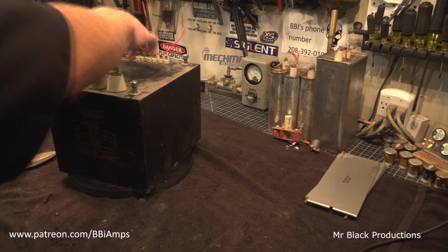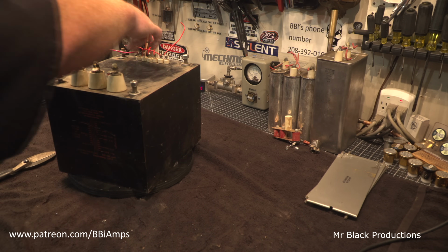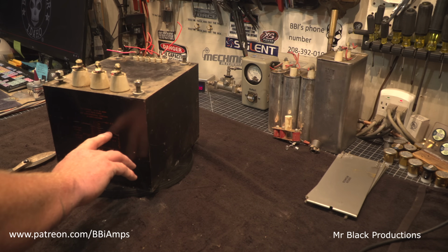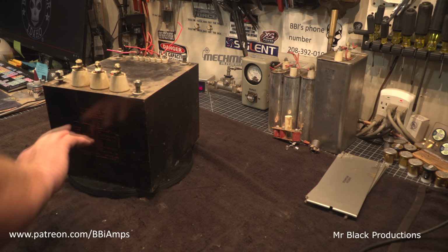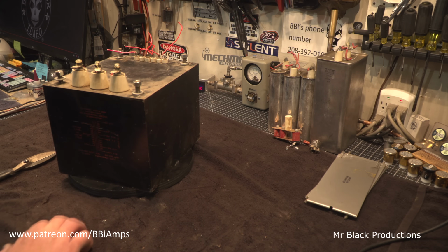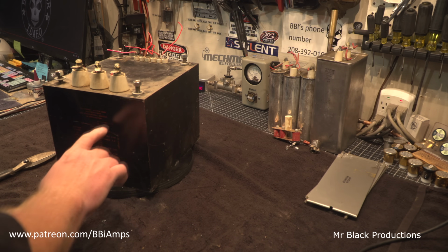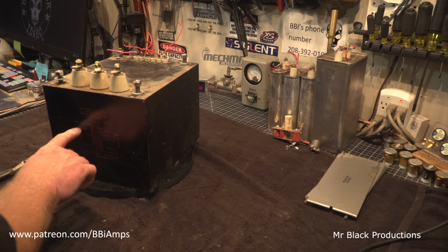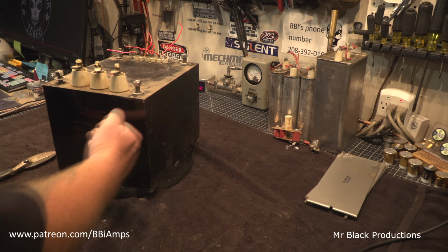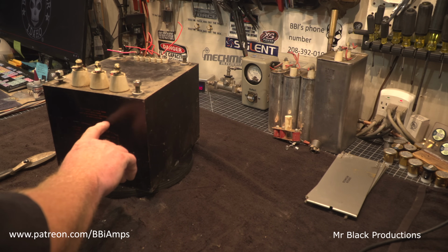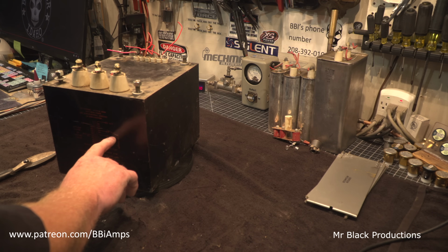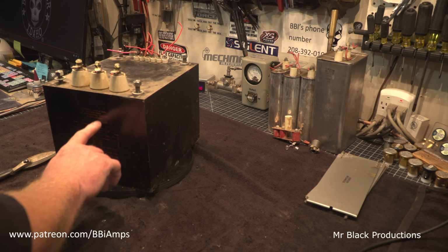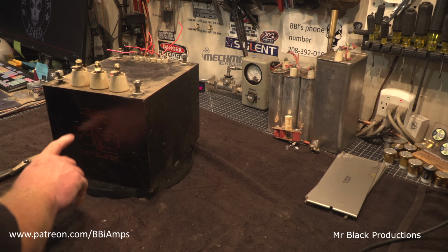0 voltage, 0 voltage, 0 voltage. Okay, so then this next tap is the 117 volt tap. So your 117 volts here, well, that's going to give us our two secondaries. That makes sense? It's only going to give us our secondaries at half that rated voltage, half the voltage if we run it up on 110. If we just use this side, so we'll say 0 and 117 volts, this particular winding will charge this to half the volts and half the amps.